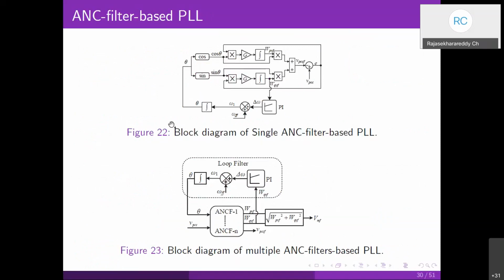Now let's have a look at the synchronization aspect of these DG inverters. We all know that we need a PLL for this synchronization purpose. In this case, I am designing a PLL using the same ANC filter. To design a PLL for the single phase system, I give the PCC voltage as input to this ANC filter, and the WQ component of this ANC filter is given to the PI controller. Under phase lock loop condition, this WQ value will be 0, and the PI controller reaches steady state when WQ is 0.